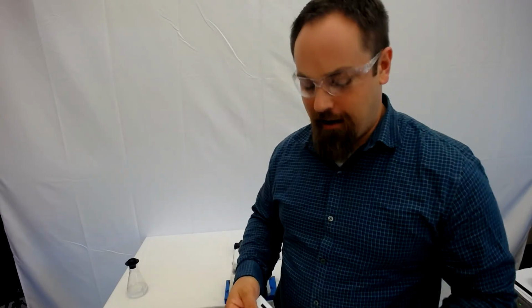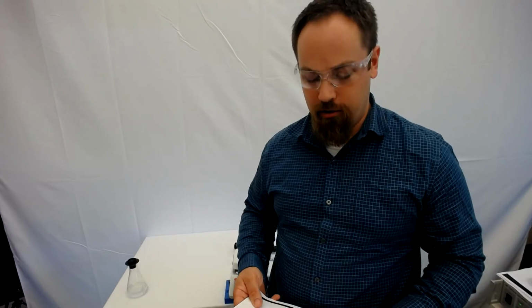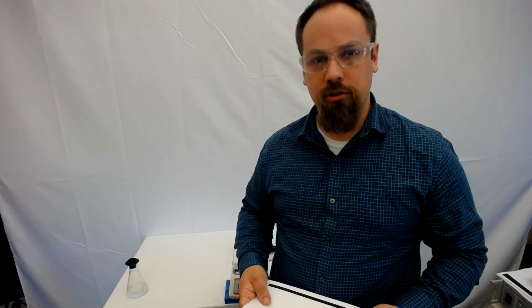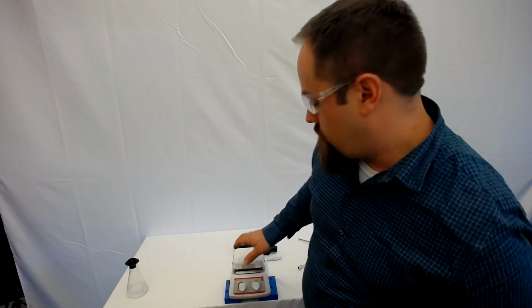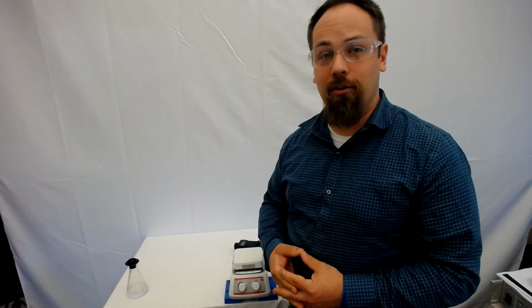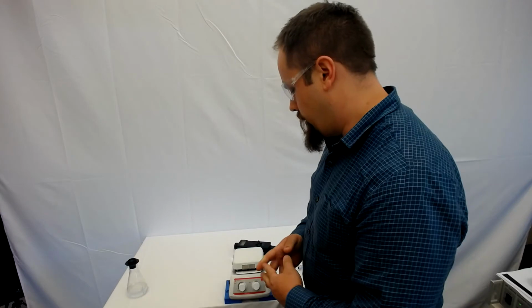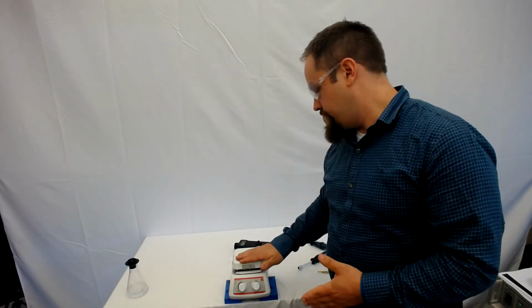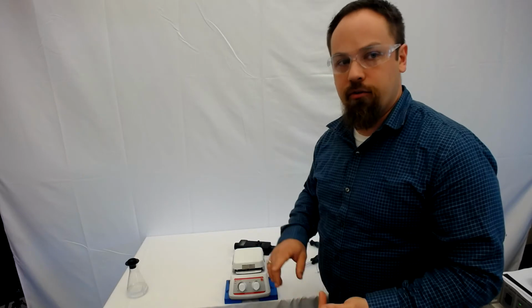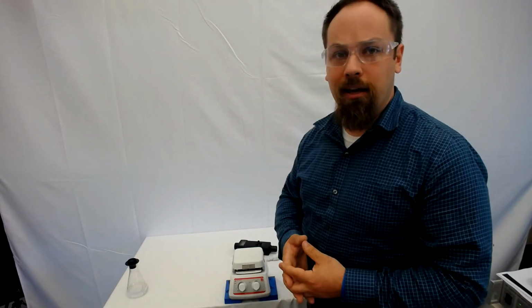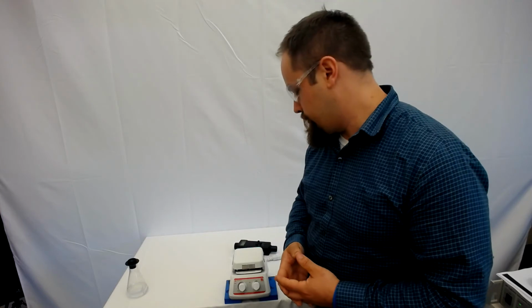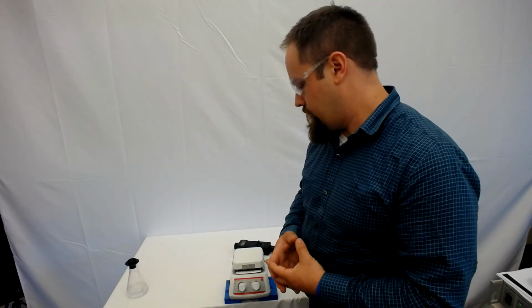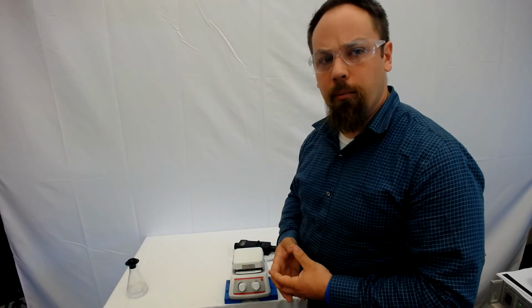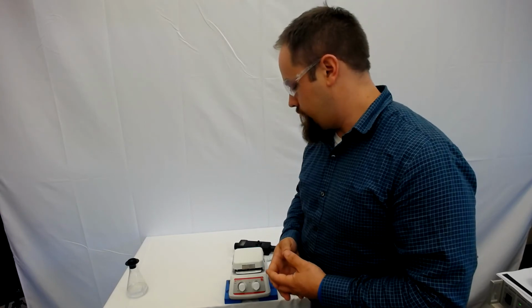Now, your final test check and packaging of the unit, you can go to your service manual for, but on every unit that we do, we're going to do a high pot test. We are going to do a visual check to make sure that it's dust-free, scratch-free, coming in at least as good as the customer returned it to us. And then we're going to pack the unit and ship it out.